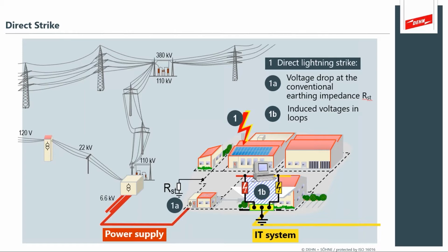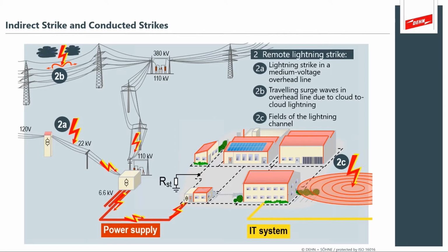And that's in conjunction with indirect strikes at a power plant, where it can strike in the ground nearby, also causing that ground swell, that ground potential rise. It can also strike the power feed and the high voltage power lines coming in and out of the system. And so you have that problem where it's an extremely large collection area. And that really leads to the discussion about bonding and equipotential bonding to control this ground potential rise.